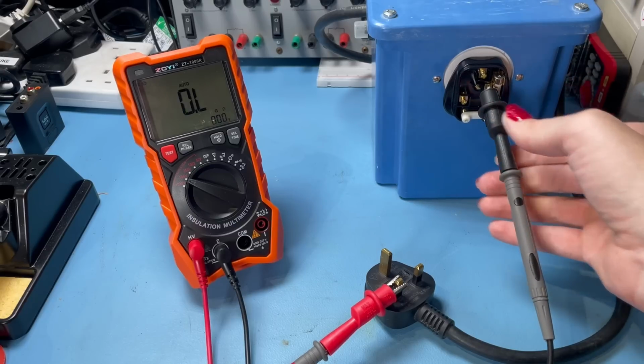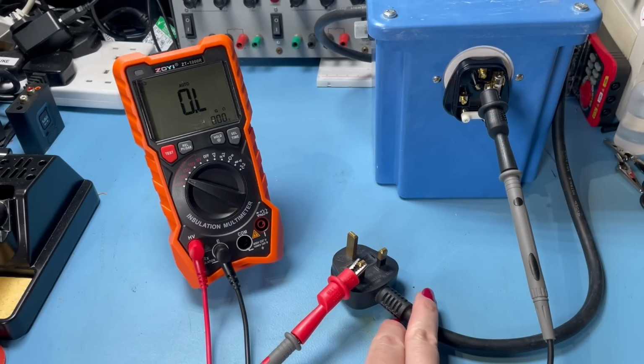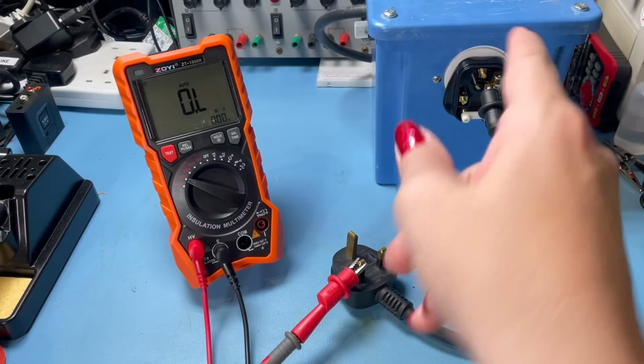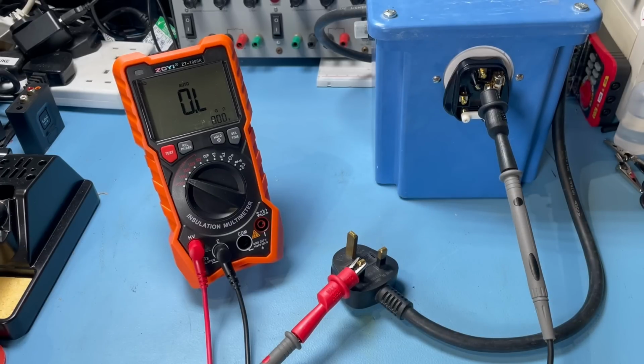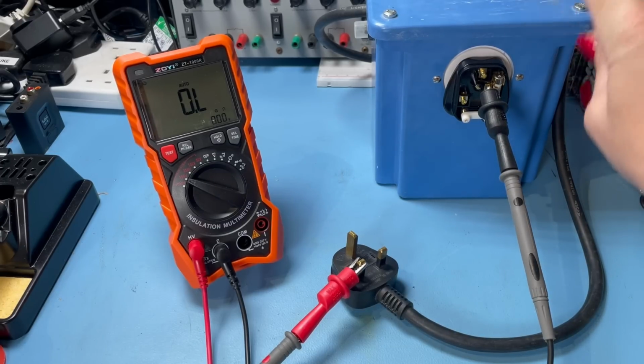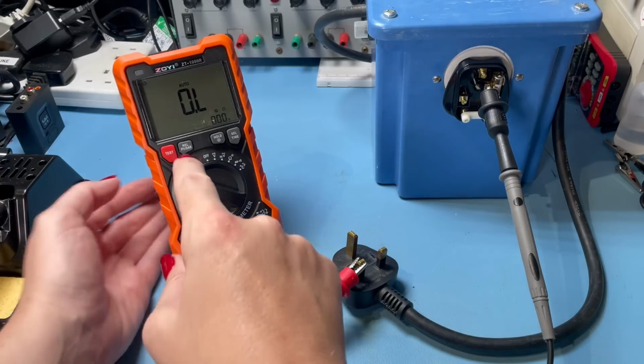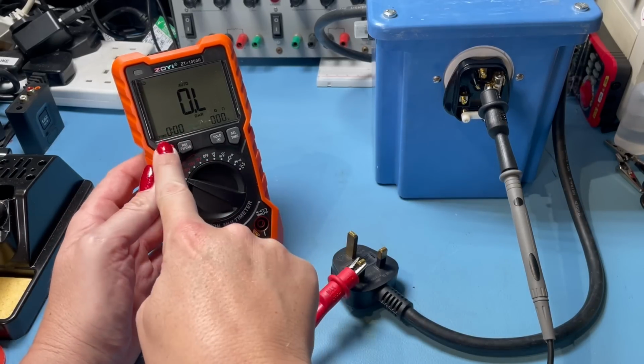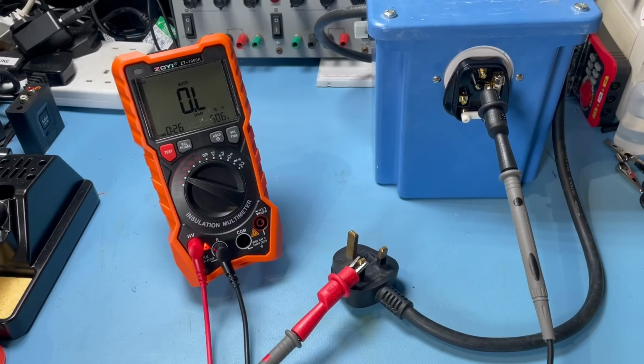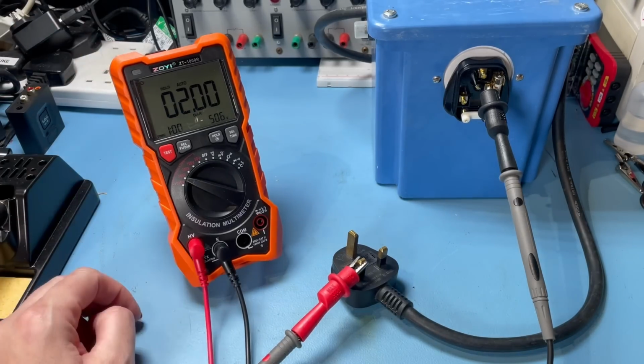I'm merely testing the insulation between the input of the transformer on the live to the output of the transformer on the live. Theory says the isolation transformer should have excellent insulation. We're going to find out. 500 volts, DAR, go. Fantastic, what a great reading. 2.00 DAR. That shows that the insulation of the isolation transformer is excellent. What a great bit of kit this is.